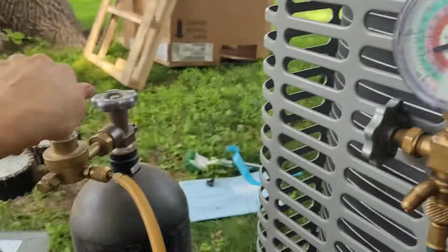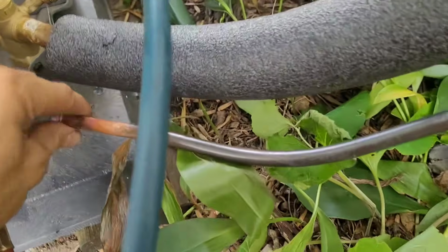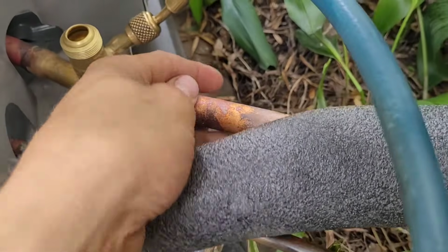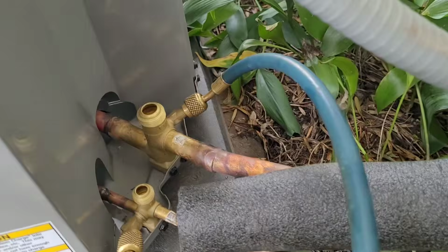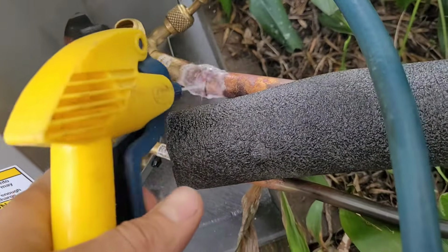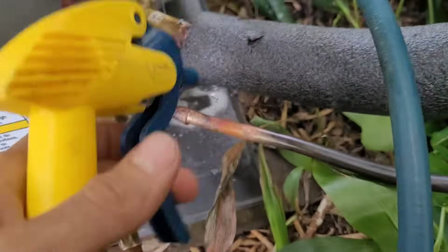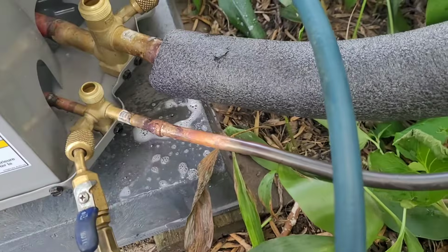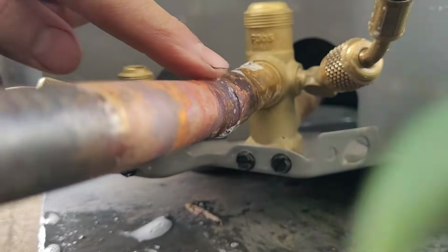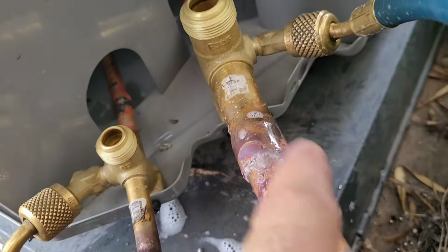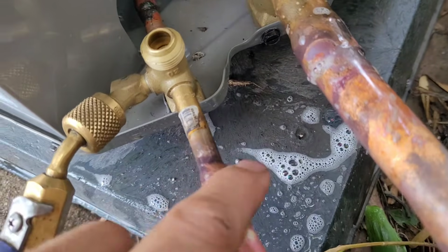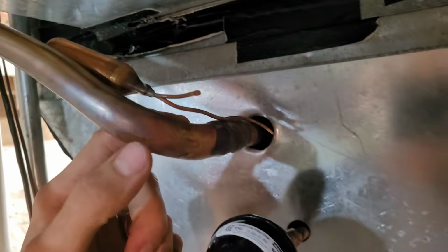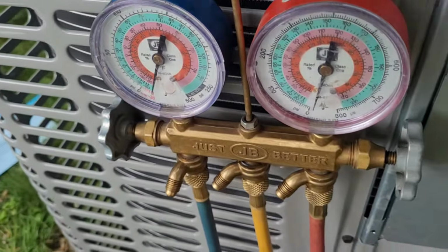Alright, so I just put a couple 100 pounds of dry nitrogen in there now that we're done brazing. And we're going to do a general leak inspection before we let the refrigerant go, using some soap and a mirror. And if we've got any significant leaks, we'll find them immediately. Or any small ones too, actually. Okay, so we're good. No leaks. In here, we're gonna go put the vacuum on. And there we are, pulling a vacuum.